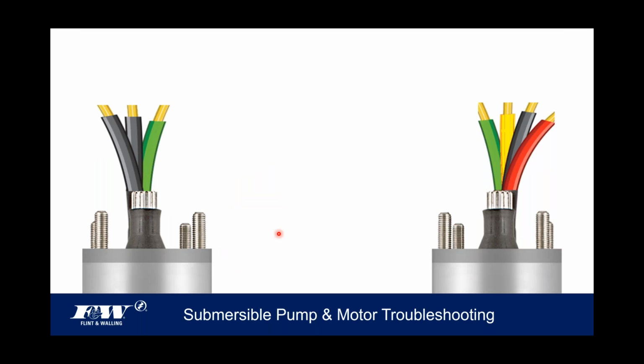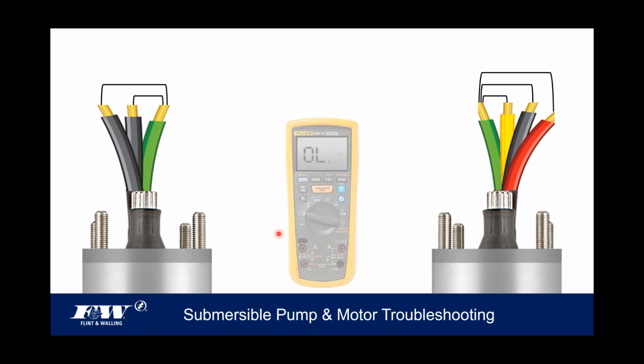All right, so if we want to check for ground, I could do this above. I could do this with the motor in the well too, but basically what I'm going to do is take my multimeter and take each lead to ground. So I'm on a 2-wire motor. I'm going to take each of those black leads, lead A to ground, and then I'm going to check lead B to ground. On the 3-wire motor, I'm going to do exactly the same thing, whereas I'm going to bring my yellow, my black, and my red all over to ground, and I'm going to take a reading of that.